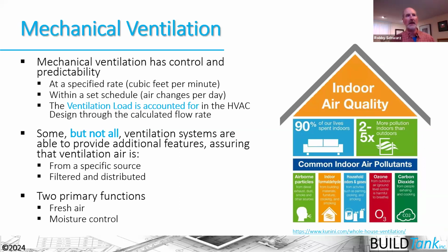So again, the two primary functions of ventilation are to provide fresh air for the occupants, and background moisture control. Now, fresh air is a bit subjective sometimes, especially maybe down here on the Front Range where we have a lot of red pollution days, or the wildfire season is starting up again in Canada, and we're starting to get some smoke coming down into the United States. Luckily, that smoke is more on the eastern coast right now, but those types of things can affect the ventilation systems and the quality of air inside of our homes. So these systems do have to have an override button so that the occupants can turn them off. But we want to be clear that those buttons and those controls need to be labeled, and we need to educate our occupants so that they understand what those systems are for, and ideally they never override them permanently.